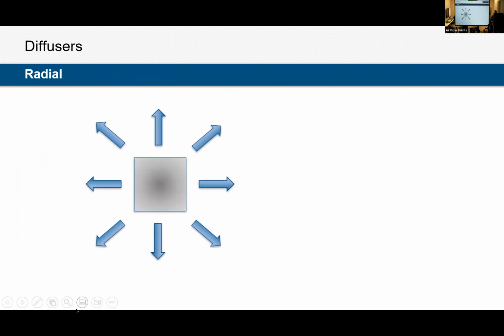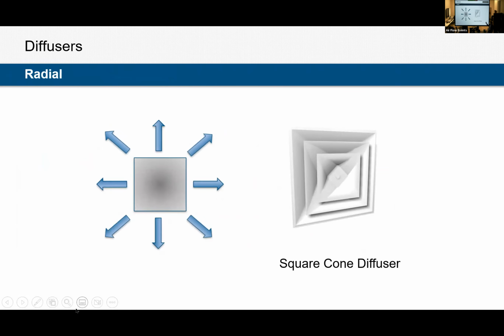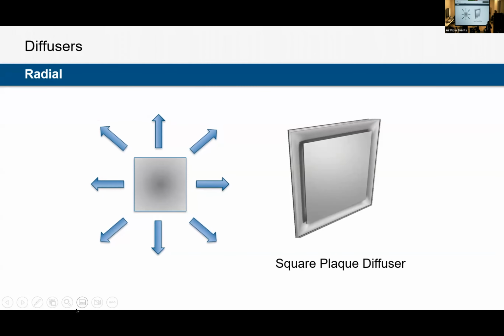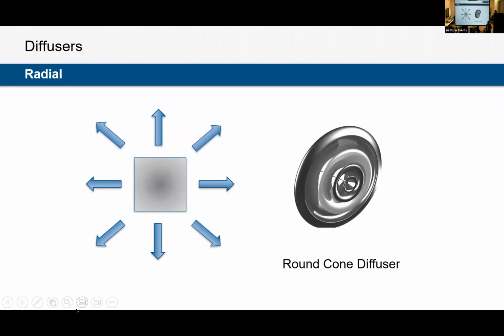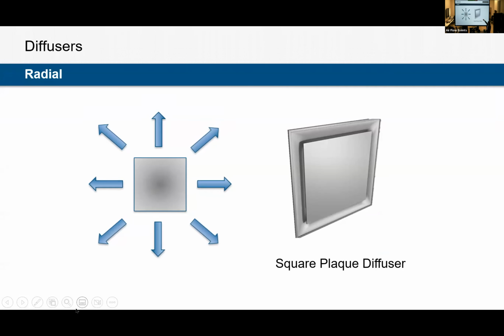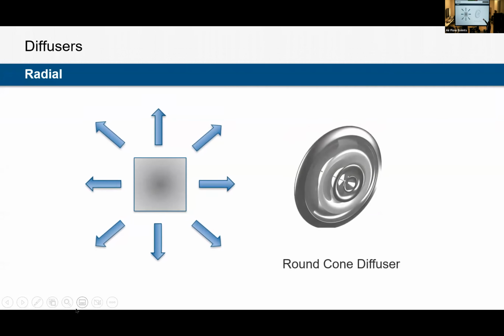The airflow pattern of diffusers. So even though we look at this, it's a square diffuser, and we would think we might get a square airflow pattern, we will have a radial airflow pattern, and that is because we have a 360-degree opening at the neck before those cones. Same thing with the plaque. Same thing with the round cone. The inside of the rectangular ones look very similar to the round cone. So you're still getting 360-degree release out of the diffuser face. It's just what we visibly see is a square.